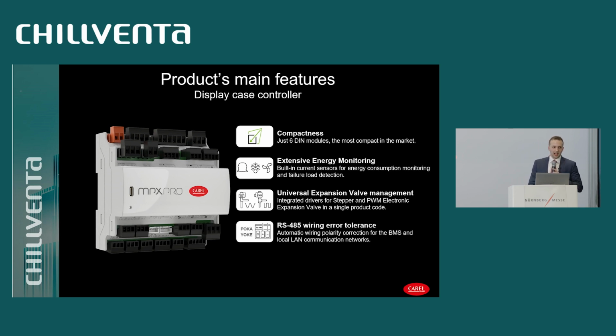Then, in order to help the service technicians, the controller has the capability to auto-polarize the BMS connection. We are perfectly aware that one of the main issues on field during commissioning is typically the communication. When the commissioning is done, quite often it happens that the whole line is offline.